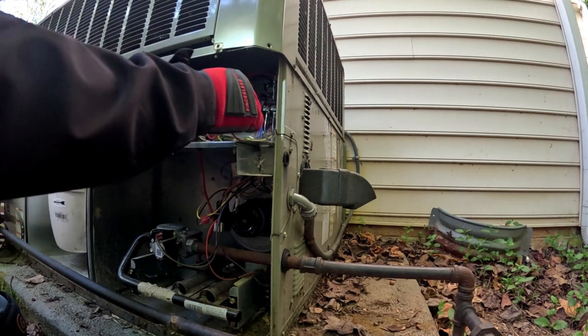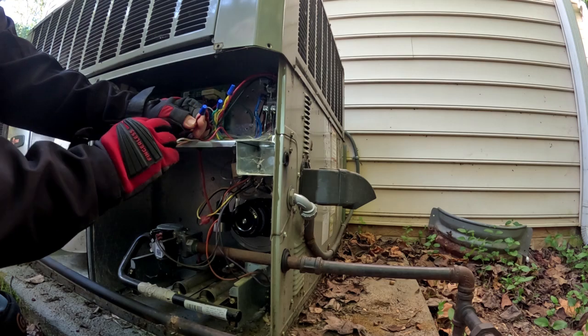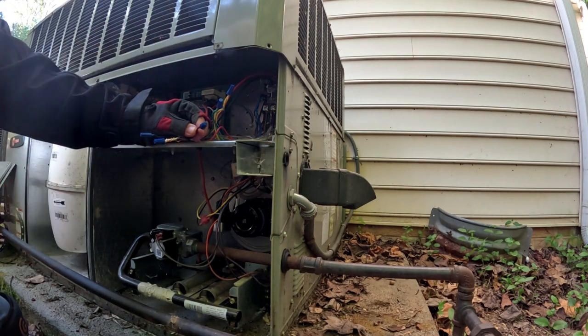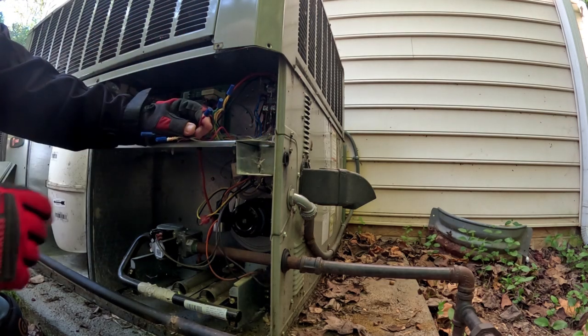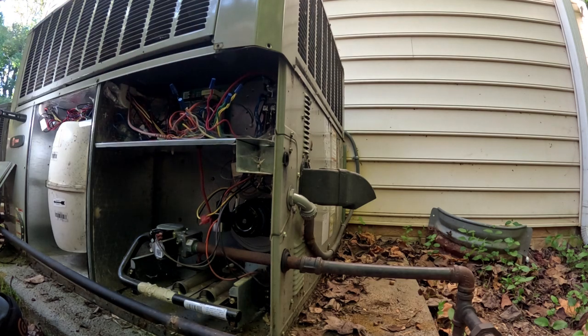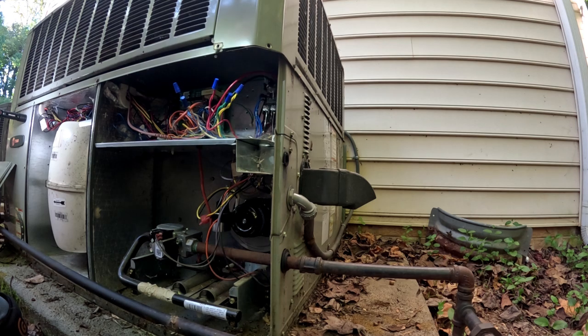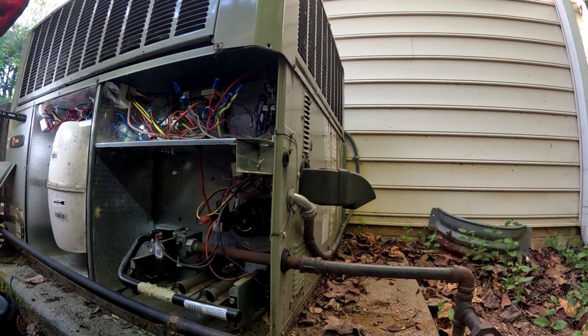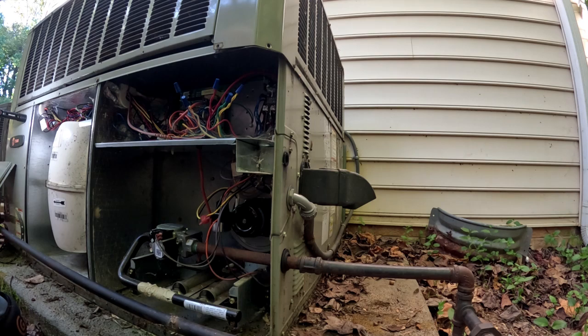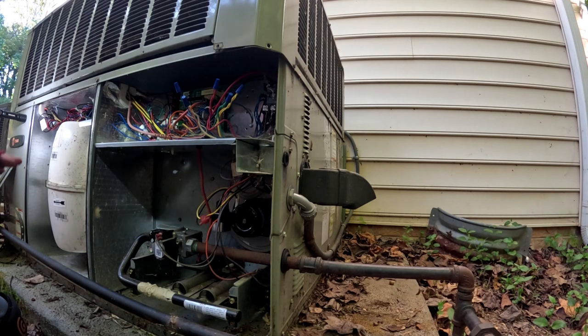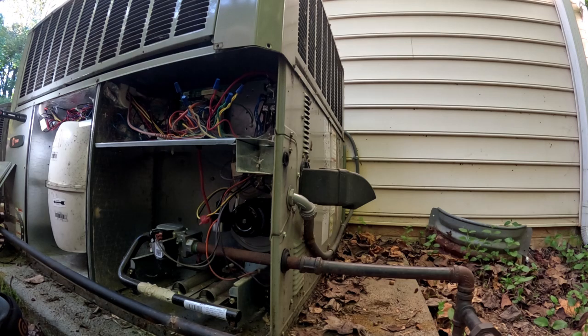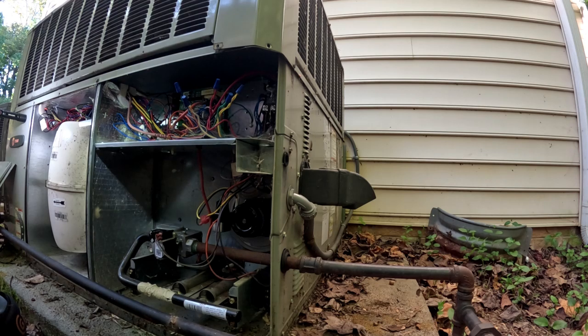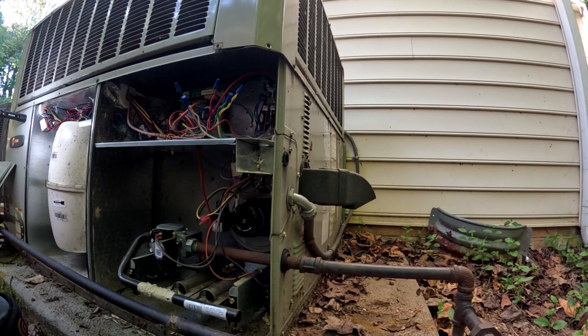Okay. Maybe it just dropped and it popped that wire and cut it so quick that it didn't trip the breaker. Hopefully it didn't damage the motor. If it was on the low voltage side and that happened, probably would have a problem in there with the relays or something, the capacitor or something inside the module on that motor, but it hit the high voltage side. Well, that's going to be internal capacitors too, I guess, if they're in that motor, but hopefully it'll work okay.